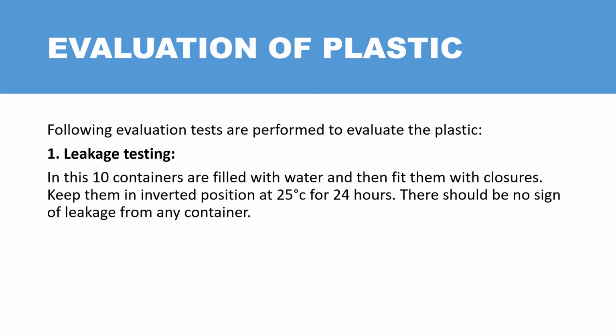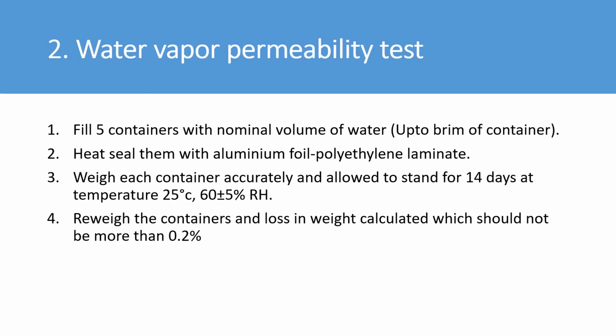So in this test, for the evaluation of the plastics, we actually take about 10 containers which are filled with water, and then fit them with the closures. Then we need to keep them in the inverted position for about 24 hours at 25 degrees Celsius. There should not be any sign of leakage from the container. Again, this is a very simple test just for checking whether the container closure integrity is being maintained.